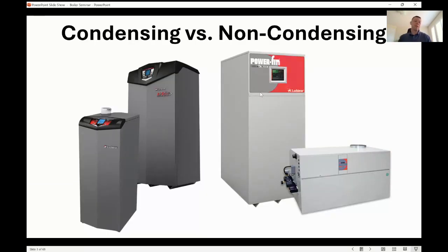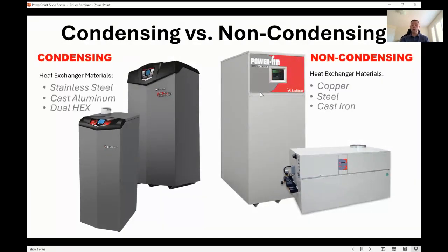So I'm going to start by talking about the difference between condensing and non-condensing boilers. What is the difference between the two? One condenses, one doesn't, I guess. The reality is they all condense. The only difference between the two is one is designed to handle condensing situations where the other is not. One of the primary things you'll see is the material or the types of heat exchangers in them. Most condensing products will be made of something that can obviously handle condensate, like stainless steel, cast aluminum, or sometimes a dual or recuperative heat exchanger design.